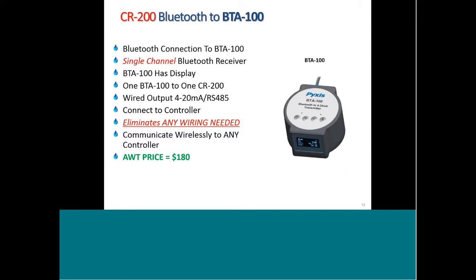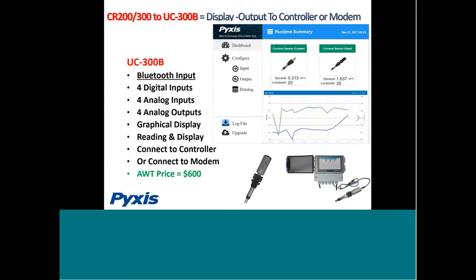data on the controller. So that's for those applications where you may want to install a corrosion sensor 250 feet away on the discharge of a condenser somewhere, and the customer is absolutely not interested in running plumbing or power or conduit or wiring to that location. You would utilize CR200 in that format with a BTA100.